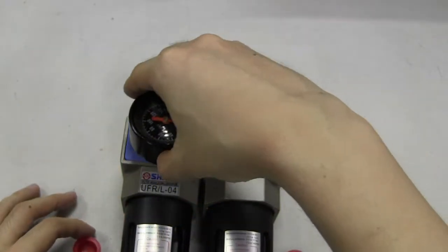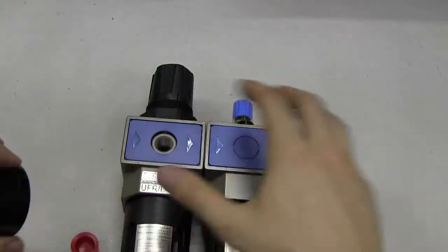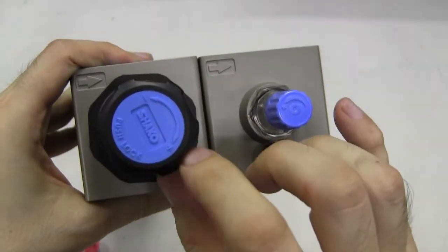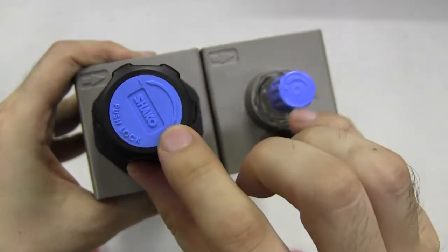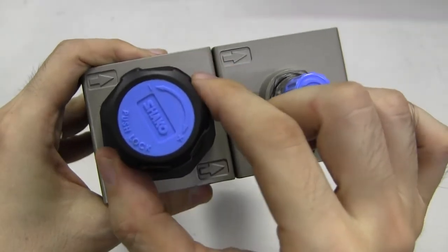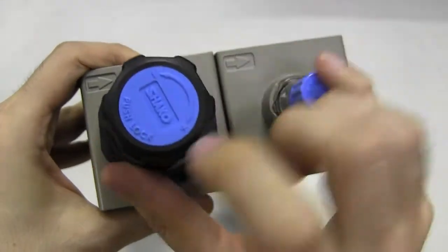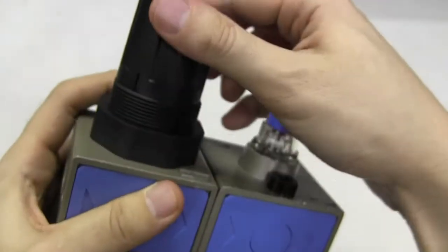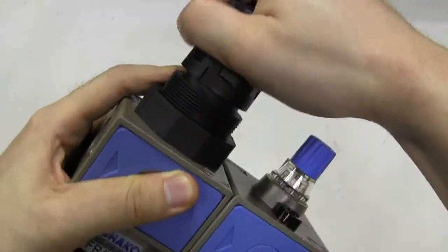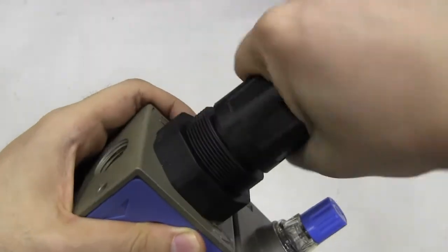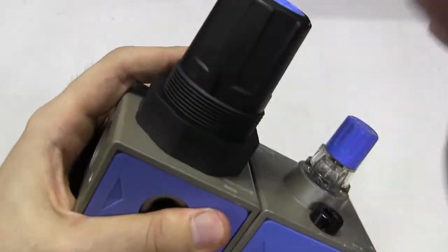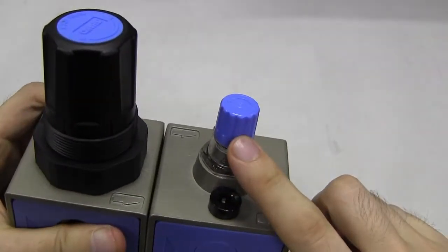For the regulator part, you see here if you turn it clockwise the pressure will go up, and counterclockwise it's going to decrease the pressure. It's a push lock type, meaning there's a lock. If you're going to change the pressure, first pull it up like this, then set the pressure that you want, then push it back.